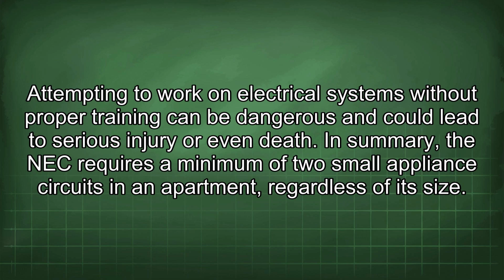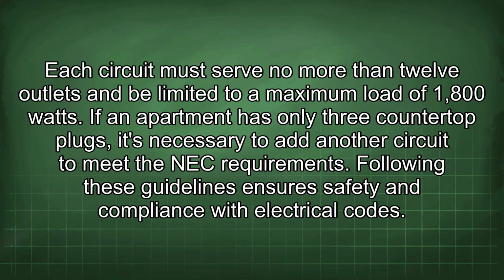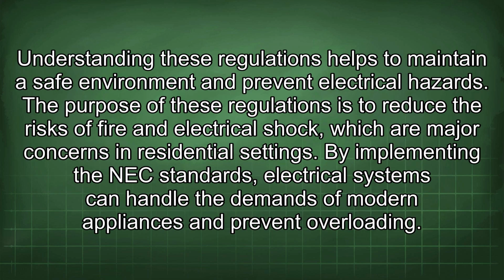In summary, the NEC requires a minimum of 2 small appliance circuits in an apartment, regardless of its size. Each circuit must serve no more than 12 outlets and be limited to a maximum load of 1800 watts. If an apartment has only 3 countertop plugs, it's necessary to add another circuit to meet the NEC requirements. Following these guidelines ensures safety and compliance with electrical codes. Understanding these regulations helps to maintain a safe environment and prevent electrical hazards.